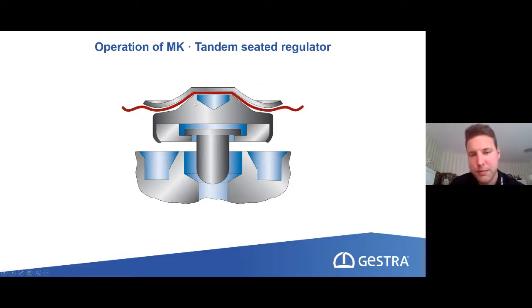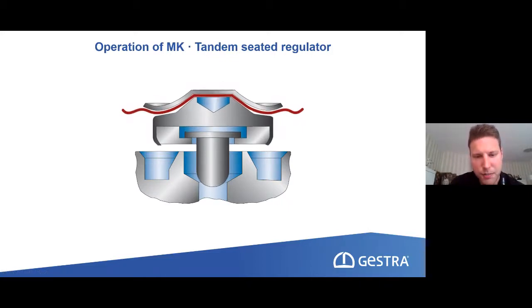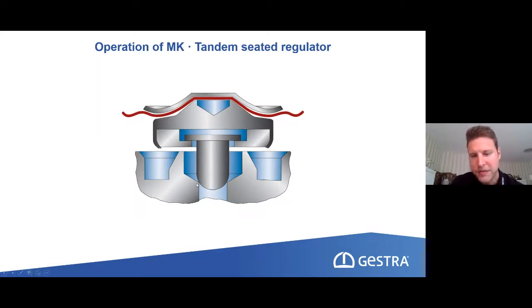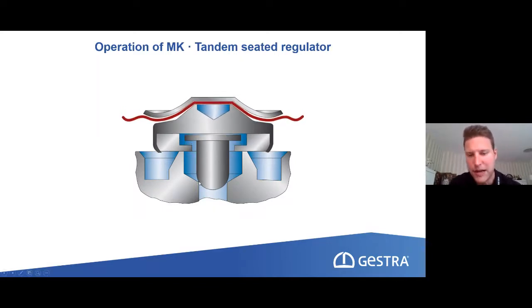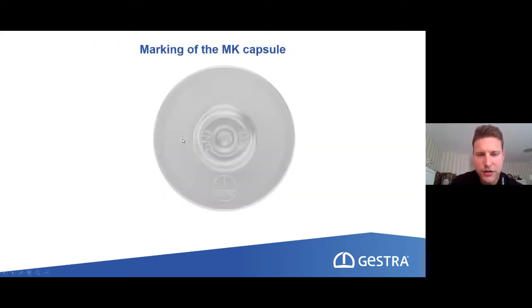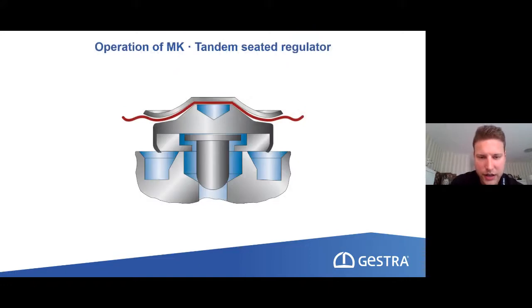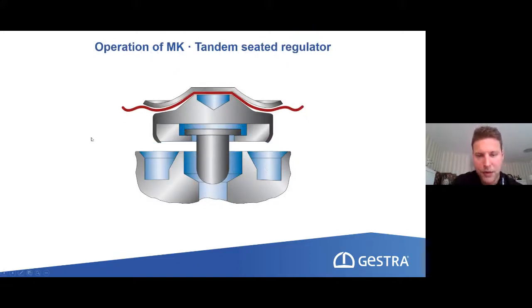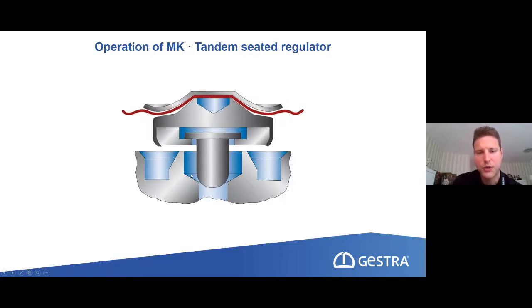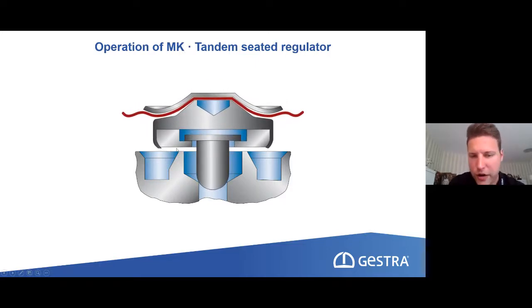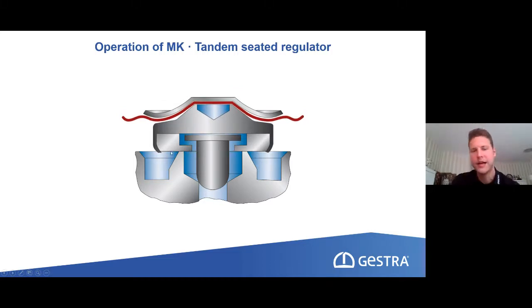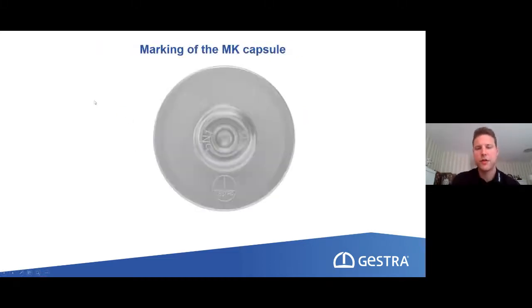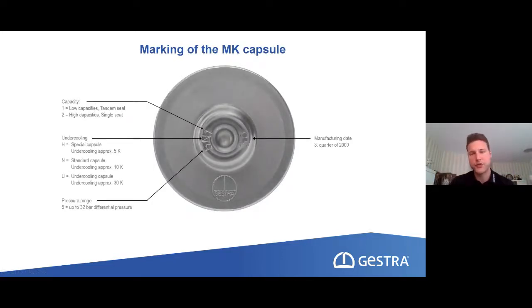And if now the steam trap starts to close, then first the plug falls into the first seat, and now we don't have any mass flow anymore. And then the second seat comes down, and the second seat can close without any flow, without any velocity here, which will guarantee that we have no wear at this part, so this surface will be fine all the time. So this additional plug is very good if we want to increase the lifetime of such a membrane. So it's also to reduce the wear of this steam trap.